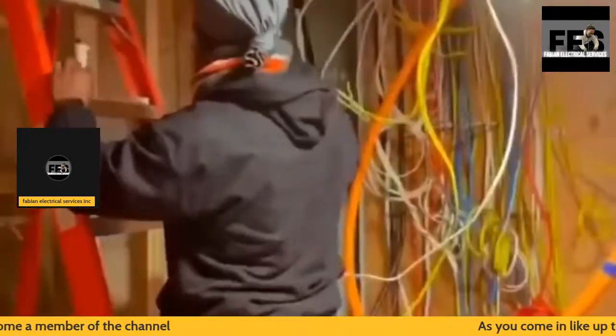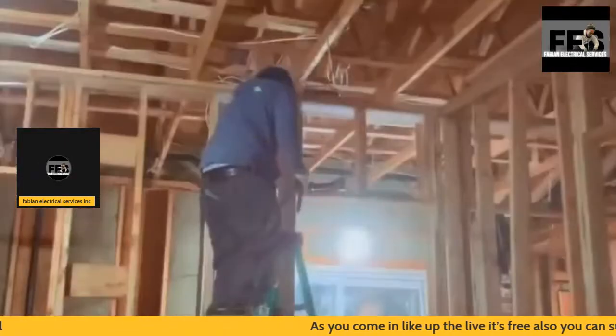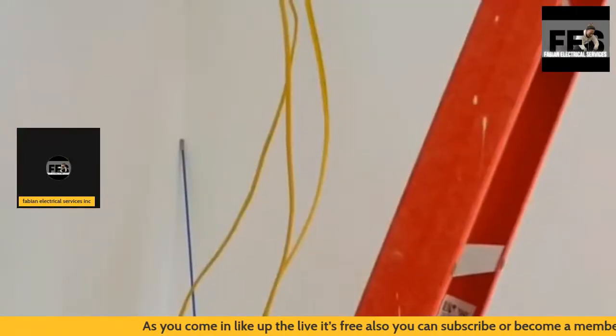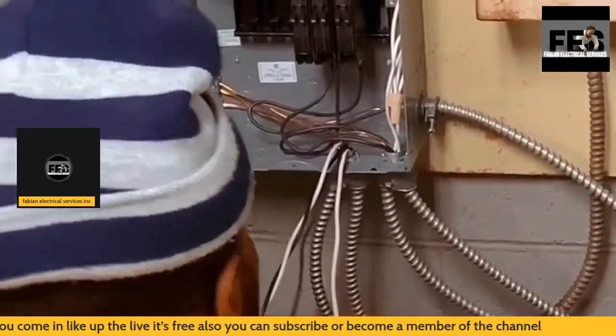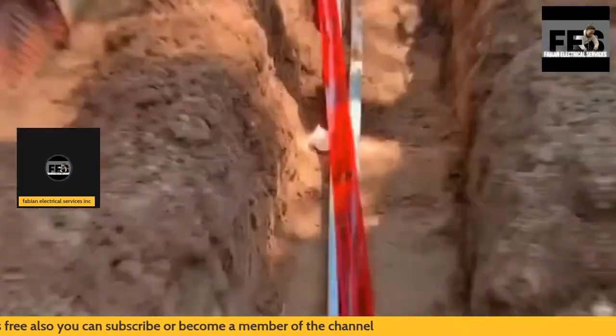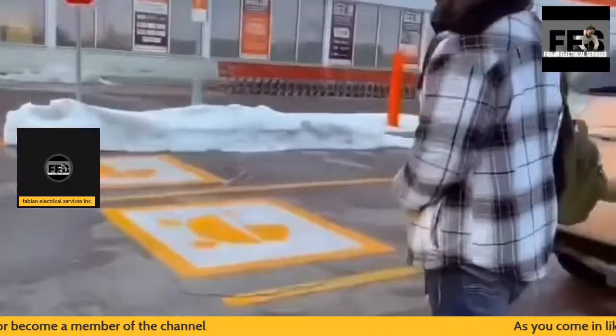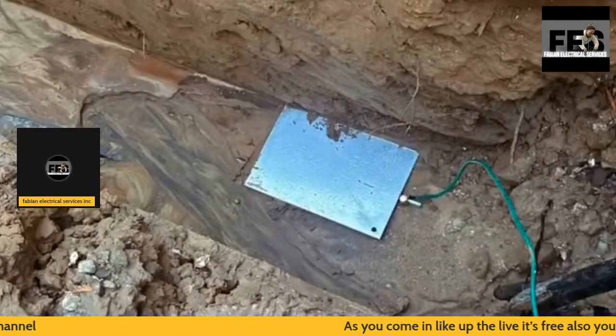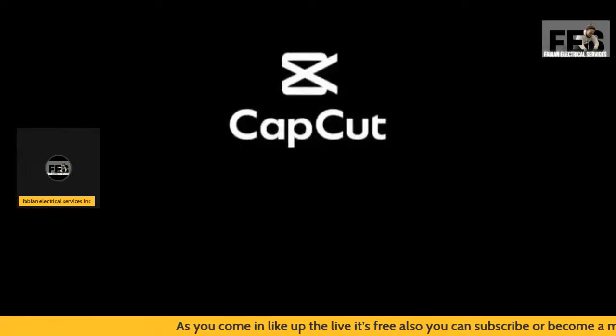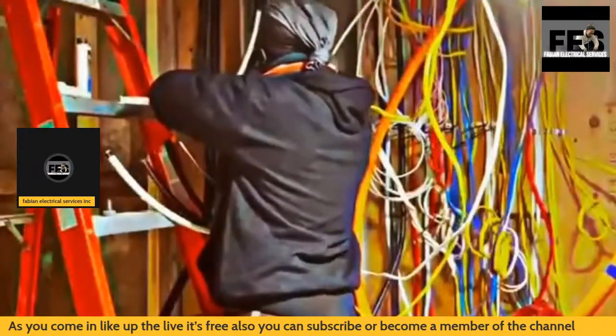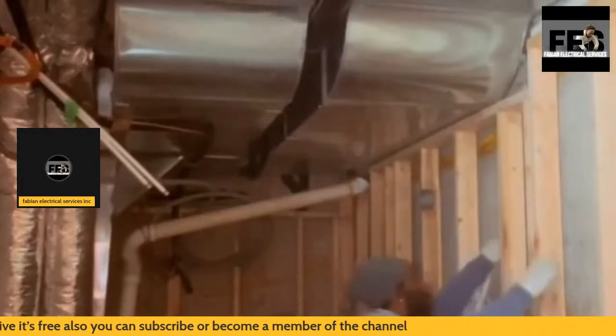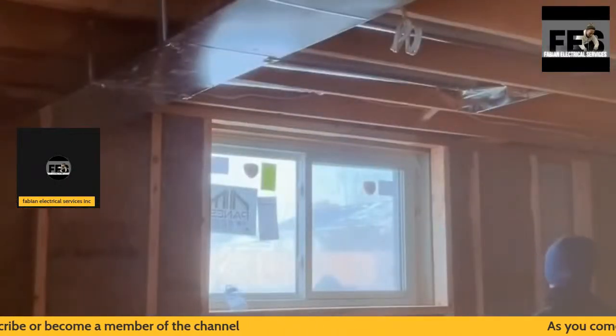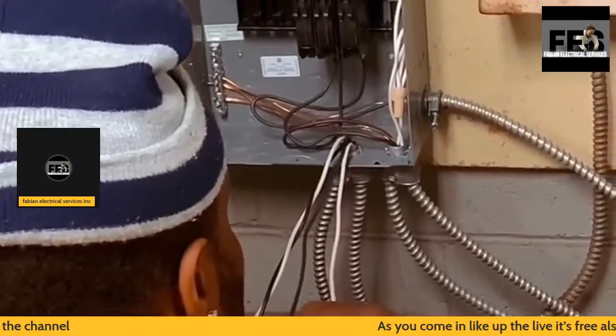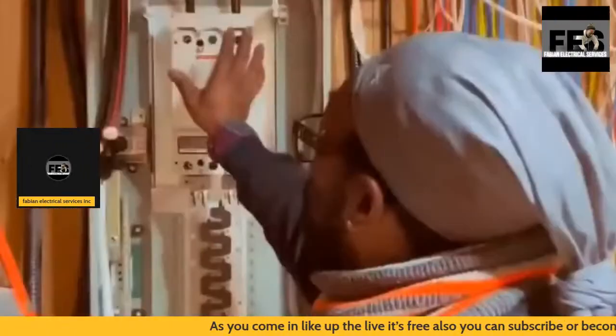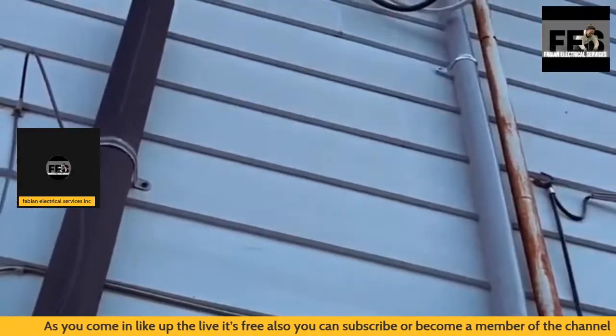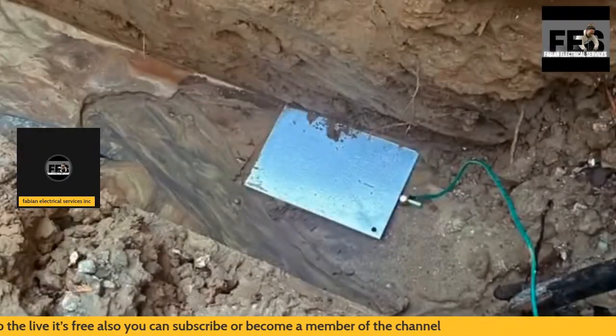The previous video was about a generator conduit installation. As you can see, my box is simply a connection point that I need to install. When it comes to the code book, I have to stay within code compliance, and those two electrical conduits I have cannot be used outdoors. So I have to change them over to a different type of piping so I can use the proper electrical installation outdoors and stay within code compliance.